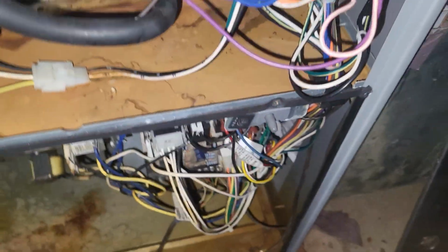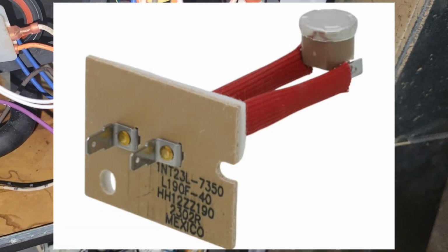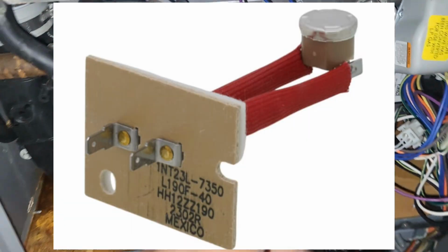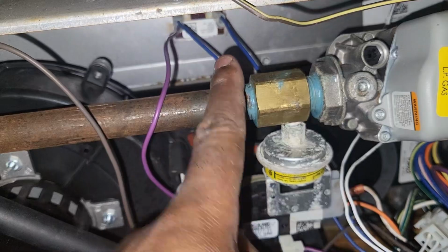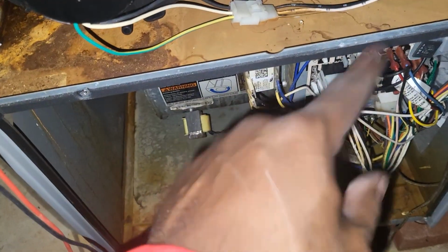And yeah, guys, in regards to what was going on, it wasn't blinking when I got here. I don't know what's going on, but I'm pretty sure there's a good chance that this unit did turn off on limit. And if the limit doesn't remake within like, what, an hour or two, I know some manufacturers could make their limit switch settings different, but if the limit switch doesn't close within a predetermined time, it's going to throw a different error, which is going to lock out the burners, and the fan is going to run and blow cold air to alert the customer that something's going on.